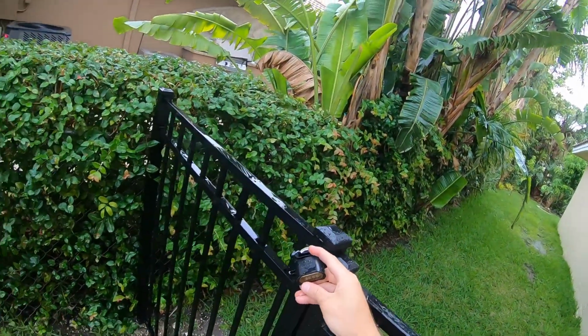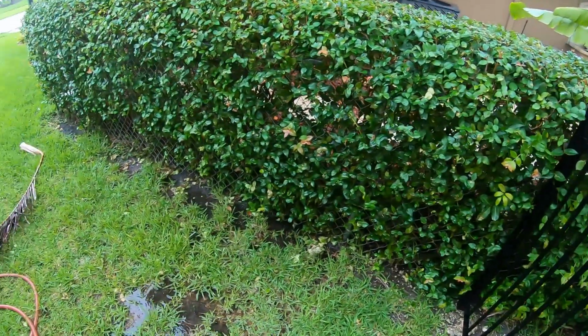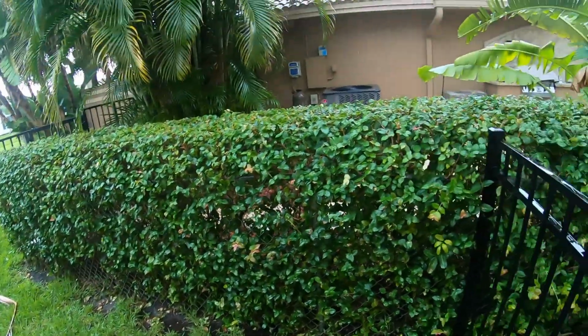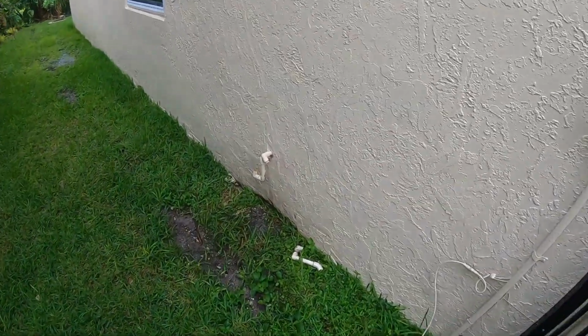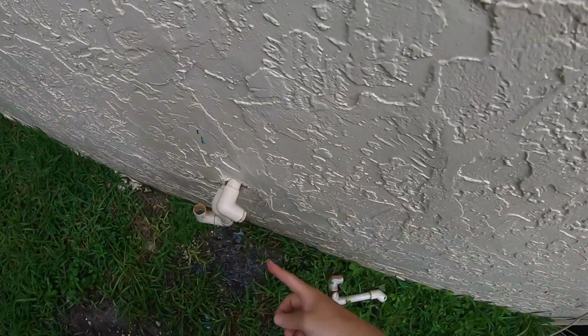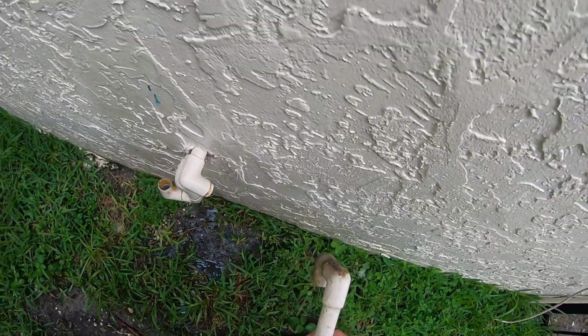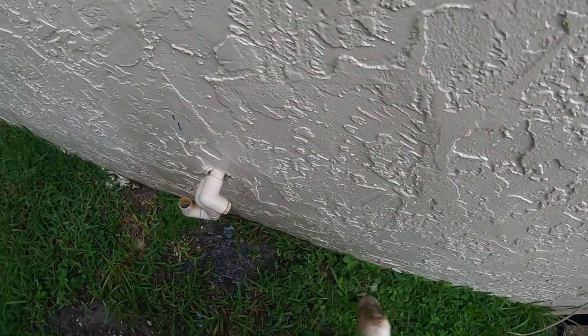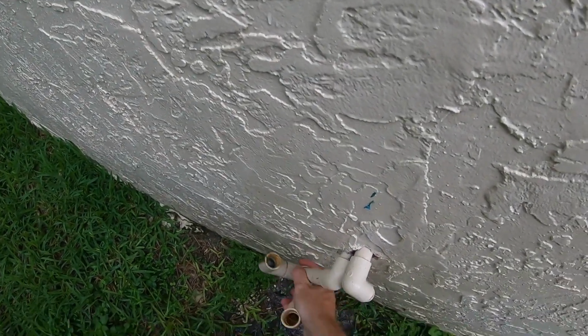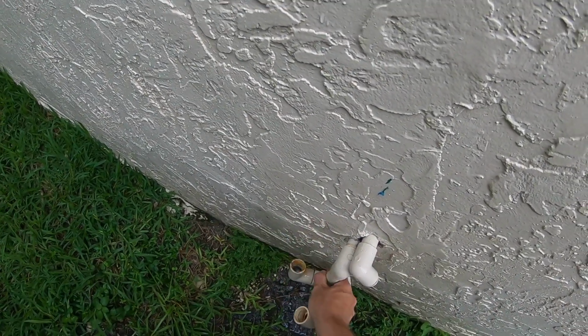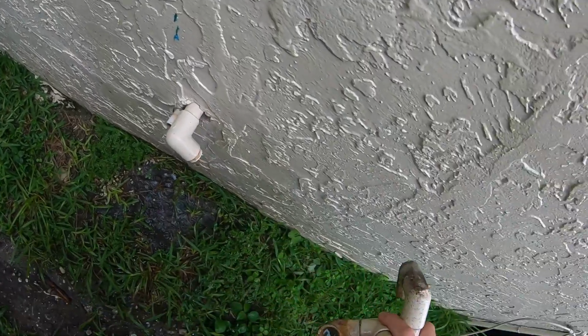Let's open up the gate. Hang on a second, I can't do this one-handed. All right, got everything unlocked. So you see here, these are the two drains. You notice there's a P-trap in there to catch all the debris. And you can see that because of the pan tablets we threw in there, this water's turning a different color and it's getting kind of murky. So the pan tablets are doing their job.